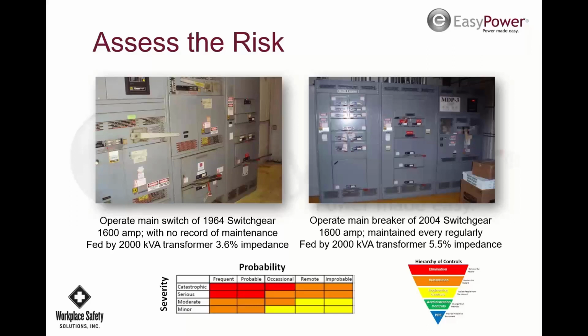But some companies are okay with the panel, and whatever's feeding the low level panels would be low levels most of the time. Not that that's always that way, but often it is. There's no requirement as to what needs to be done as long as you can assess the hazard based on your system. So if all the disconnects on the floor are 30 amp disconnects that are hazard category 0, fed by this low level panel, and everybody that works there knows that, that's okay. It would be good probably to have some label to say that it is low level to be sure.